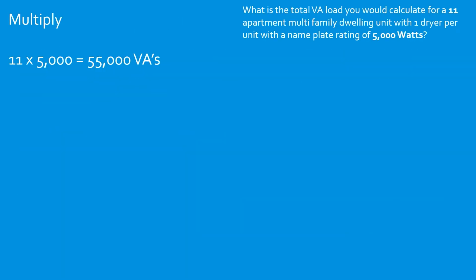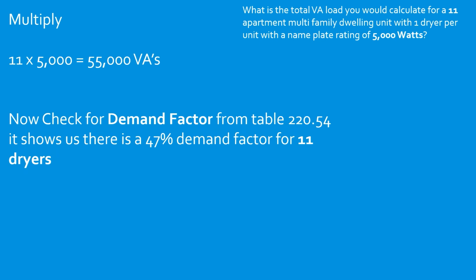All right, so the first thing that we're going to do is find our total VAs. We have 11 dryers at 5,000 each, so we're going to bear that math out first before we even worry about demand factors. So we bear that math out and find out what our total VAs are. Now we're going to check for demand factors and find out if there are any. We're going to head to table 220.54 because it's dryers.